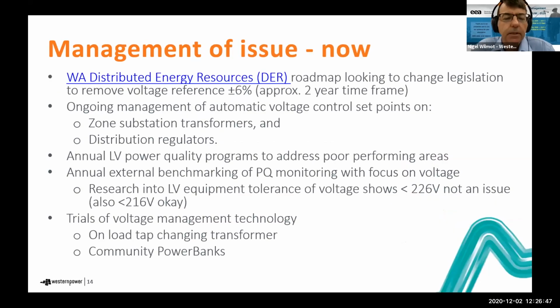So at the moment, the number one challenge for us is our tight range. The WA Distributed Energy Resources Roadmap has foreseen that they will change the legislation to remove the voltage reference of plus minus 6%. And the most likely outcome there is they'll go to the Australian standard, which is plus 10 minus 6%. Western Power and others, and ENA members, will be looking at changing the Australian standard to the full international range in the coming years.